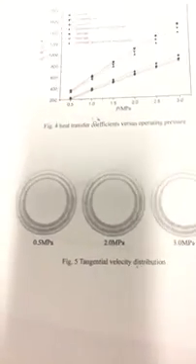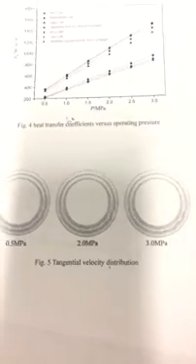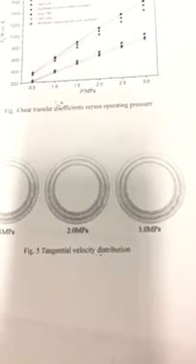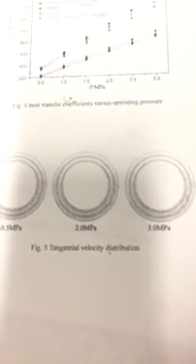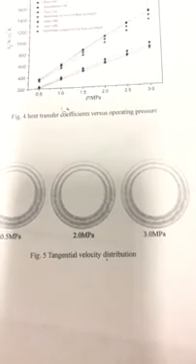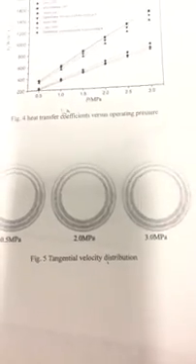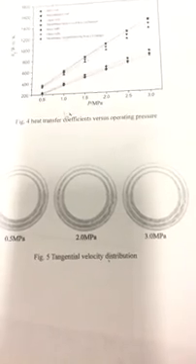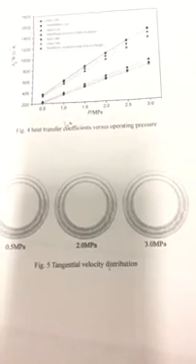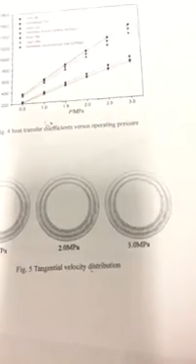Finally, we see the conclusions. The major findings are, first, the gas tangential flow in membrane helical-coil heat exchangers is significant to heat transfer enhancement. The average heat transfer coefficient of the membrane helical-coil heat exchangers is higher than that of the membrane serpentine-tube heat exchangers under the same conditions. Secondly, operation pressure does not have any influence on the velocity field in heat exchangers. However, high pressures can improve heat transfer through the increase of the syngas mass flow rate.